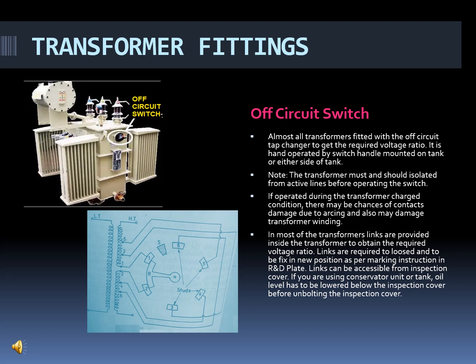It is hand operated. Please note, the transformer should be isolated from the active lines before operating the switch. As it is an off-circuit switch, the supply to the transformer shall be disconnected before operating it. If operated while the transformer is charged, there may be chances of contact damage due to arcing, and it may also damage the transformer winding. Which means when the supply is live, if you operate the off-circuit switch, there are chances of contact damage due to arcing, or it may damage the transformer winding also. Hence, the off-circuit switch can be operated only in the isolated condition.